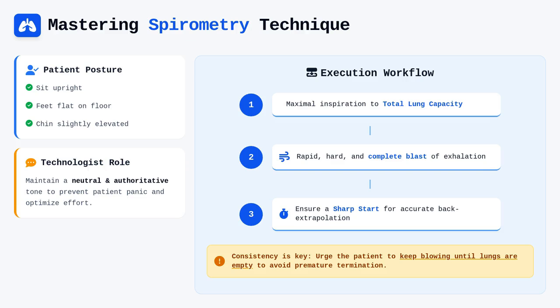Achieving high-quality spirometry data depends entirely on the technologist's ability to guide the patient through a series of specific, high-effort respiratory maneuvers. The process begins with proper posture, which requires the patient to sit upright with their feet flat on the floor and their chin slightly elevated to ensure an open airway. It is imperative that you maintain a neutral and authoritative tone when giving instructions, as panic or poor communication can lead to suboptimal efforts. You must prepare the patient to take the largest possible inspiration to total lung capacity, followed immediately by a rapid, hard, and complete blast of exhalation.